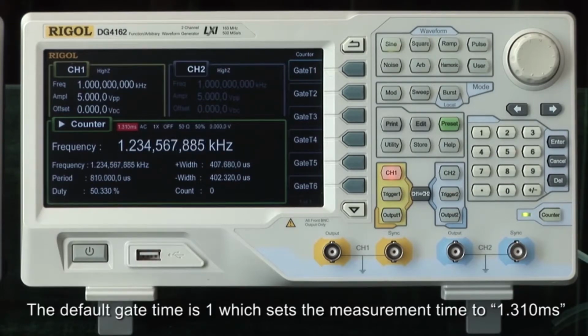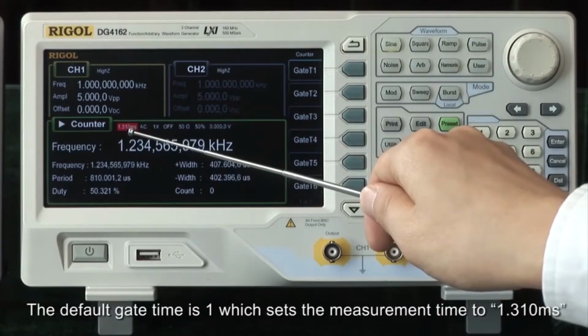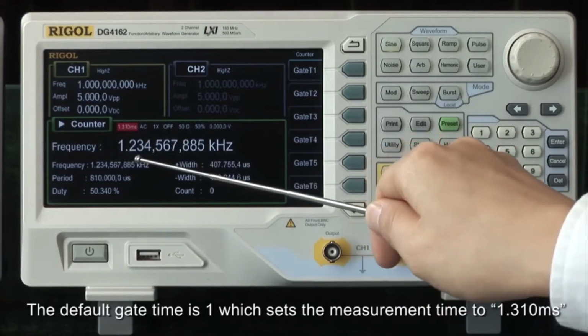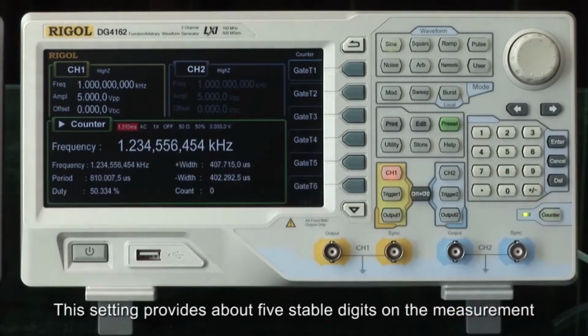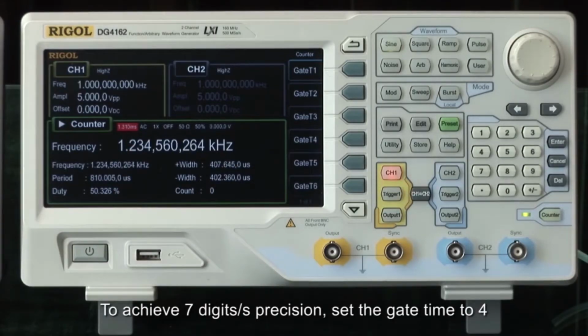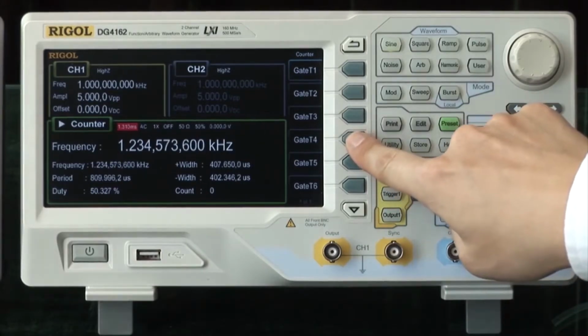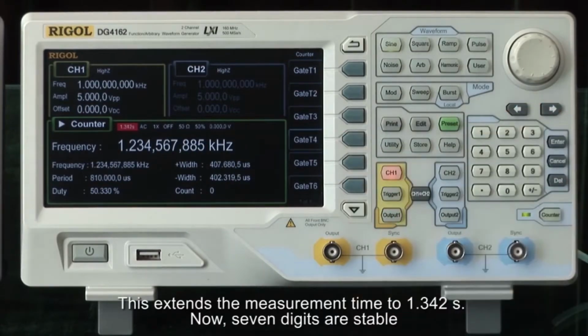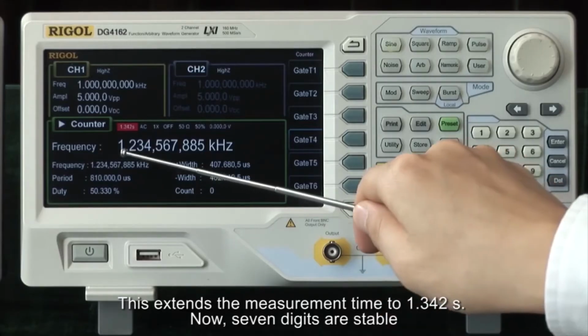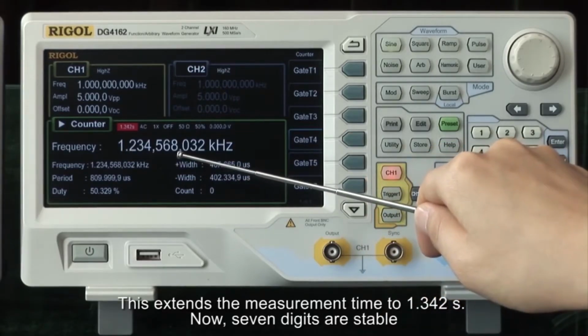The default gate time is 1, which sets the measurement time to 1.31 milliseconds. This setting provides about 5 stable digits on the measurement. To achieve 7 digits per second precision, set the gate time to 4. This extends the measurement time to 1.342 seconds, and now 7 digits are stable.